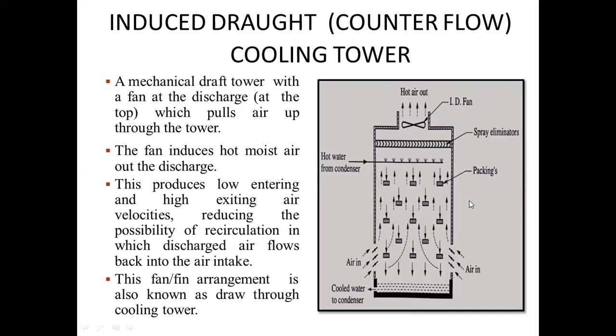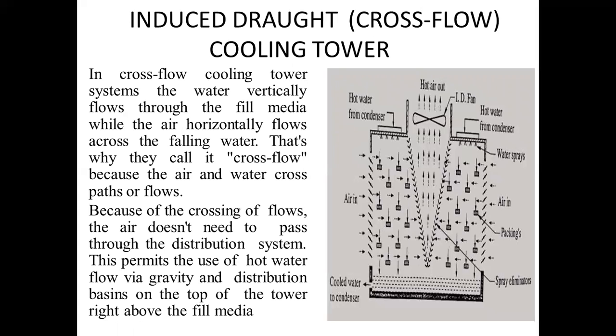Induced draft cooling tower. In case of an induced draft cooling tower, we are using a fan at the top of the cooling tower. It is a mechanical draft tower with a fan at the discharge which pulls air, or which induces the vacuum. The fan induces hot moist air out through the discharge. This produces low entering and high exiting air velocity, reducing the possibility of recirculation, in which discharge air flows back into the air intake. This fan arrangement is also known as a draw-through cooling tower. Induced draft can be of cross flow. You can say in this case, induced draft tower cross flow.